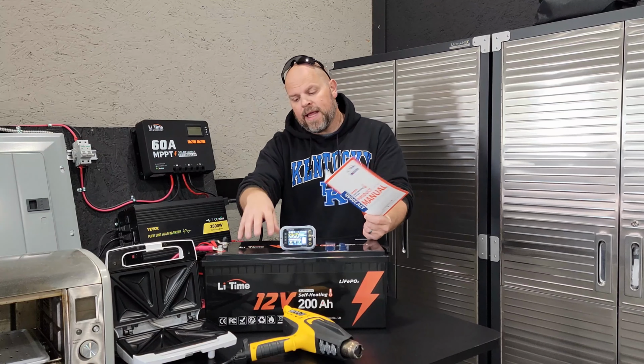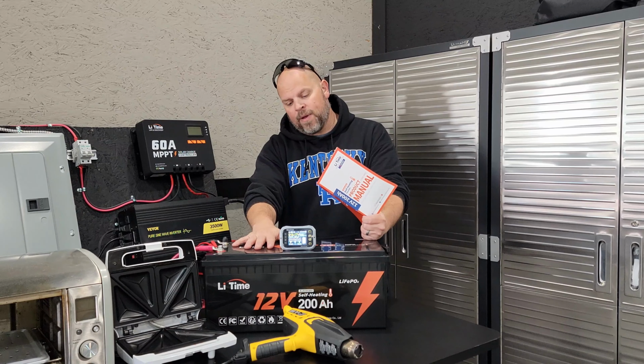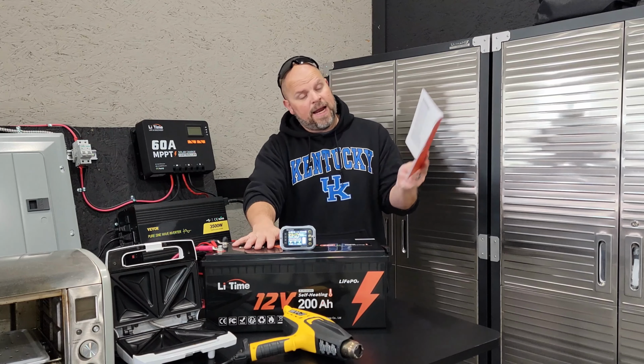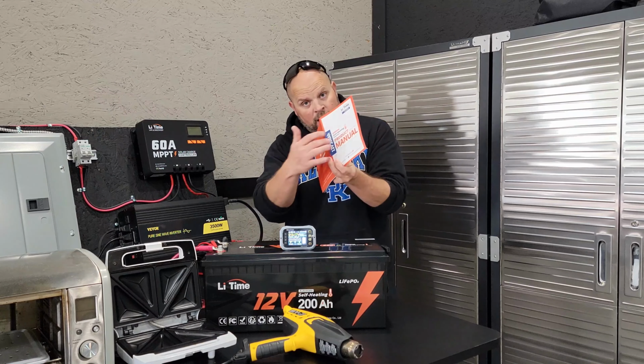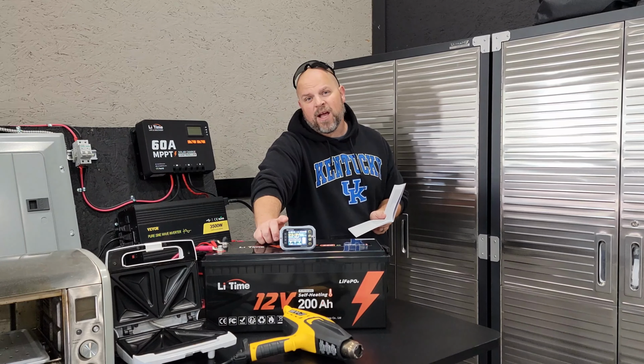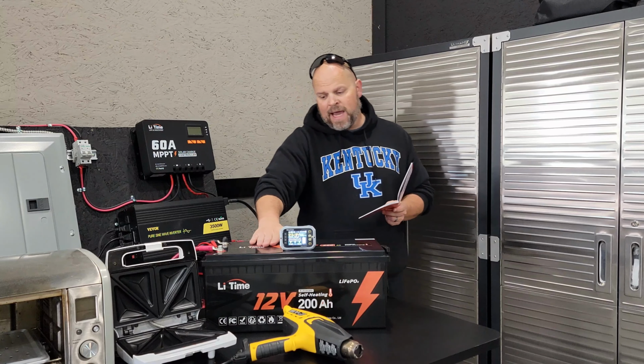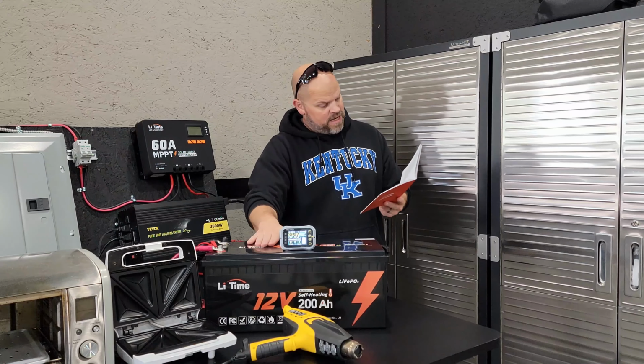Somewhere I read that this was a 200 amp BMS, but as I'm looking in the product manual, it's telling me it's a 100 amp BMS. Now there's a problem, because I've just run this for several minutes running close to 300 amps, and the top of this battery is pretty hot.